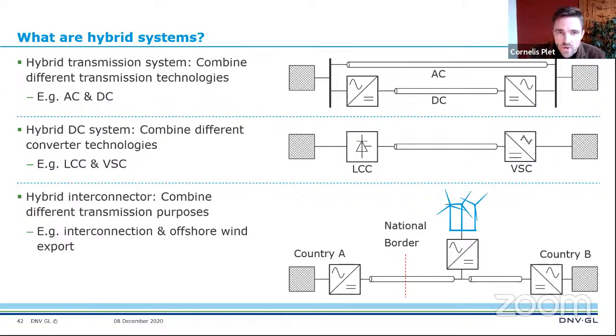Next up is a hybrid HVDC system—an HVDC system in which different converter technologies are mixed, for example classic line commutated converters (LCC) and more modern VSC converters. This tries to exploit the LCC aspects of low cost, high capacity, and fault blocking capacity, combined with the benefits of VSC: low footprint, low AC grid impact, and a high level of controllability. Of course, combining different technologies can also have drawbacks, such as differing fault behavior between LCC and VSC converters, and power flow direction.